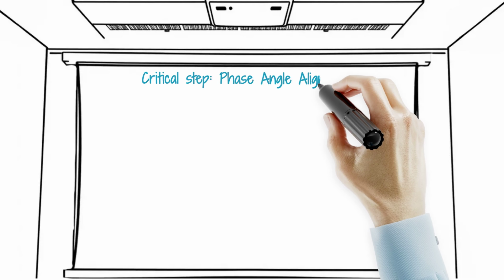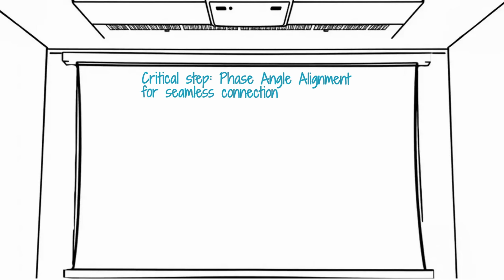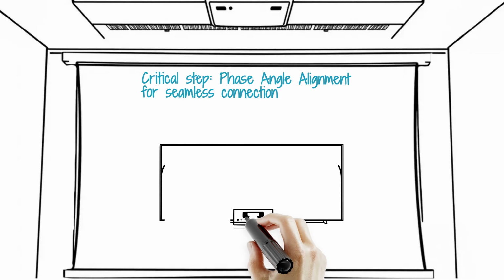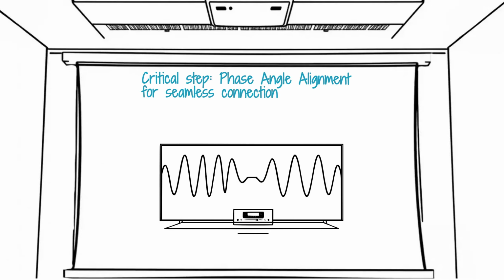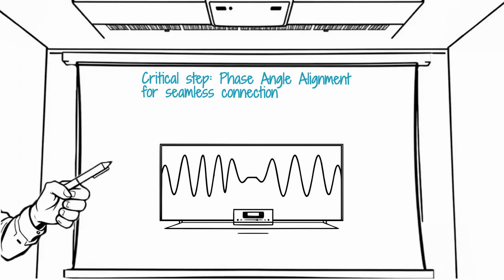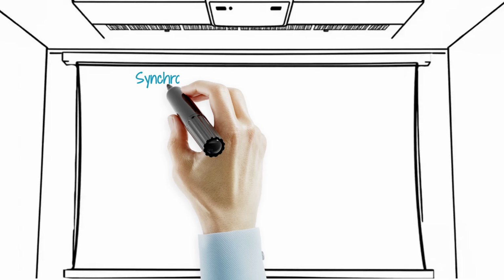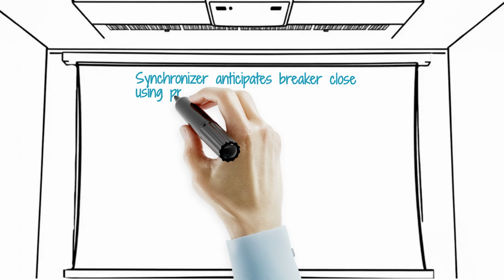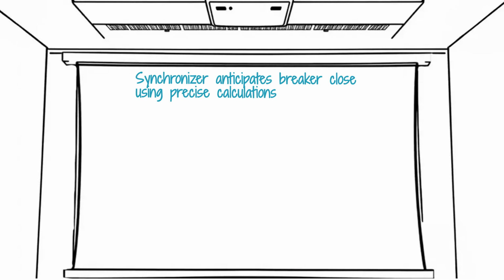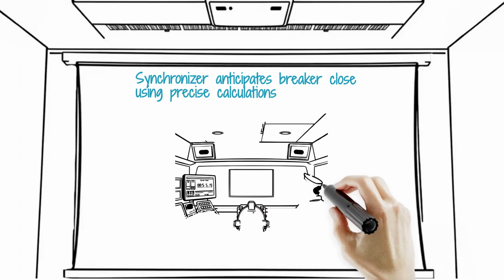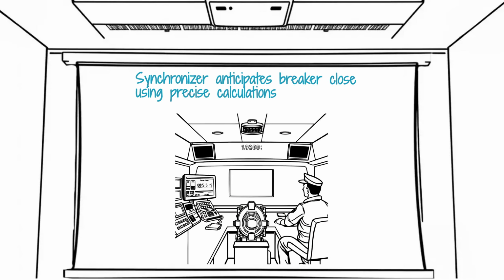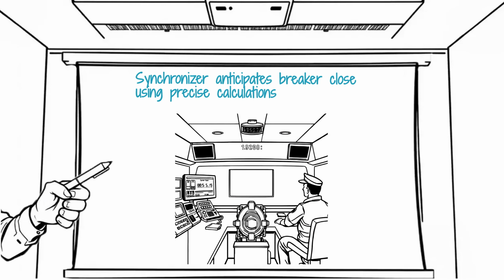Third, and most crucial, is phase angle alignment. The synchronizer monitors the phase difference between the two electrical waves. It must wait until the two waves are perfectly in phase, meaning the phase angle is 0 degrees. To achieve this, the synchronizer acts as a high-speed calculator. Knowing the mechanical closing delay of the circuit breaker, the fraction of a second it takes to physically close, the unit issues the breaker close command precisely ahead of time. It anticipates the zero crossing.